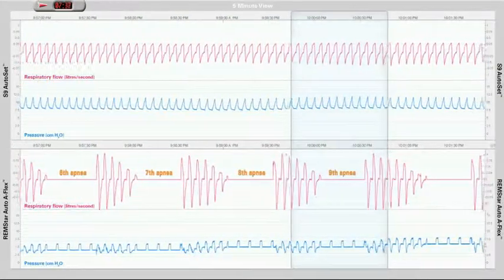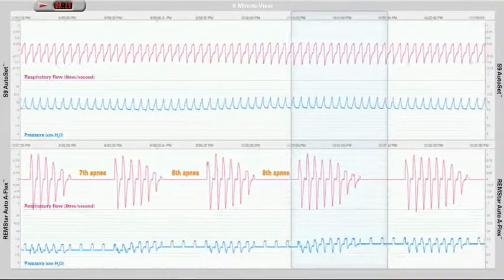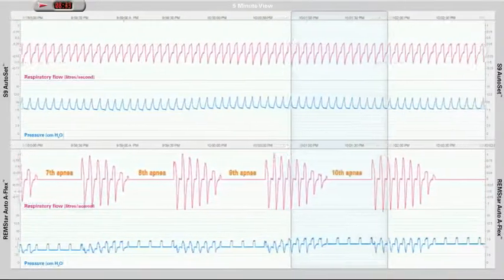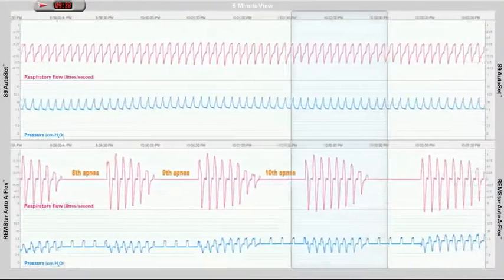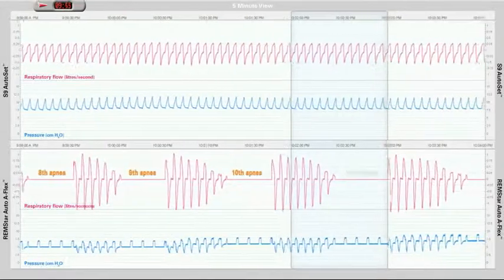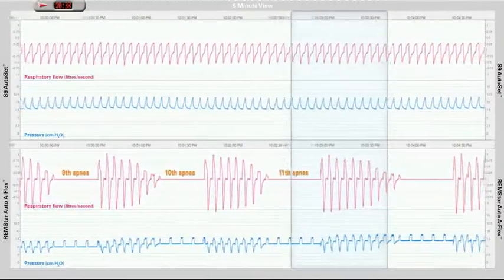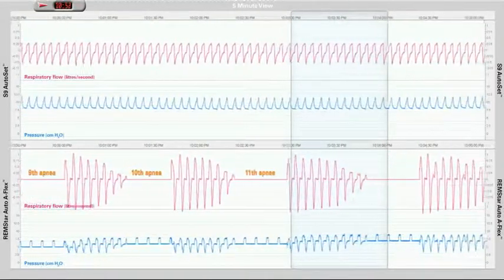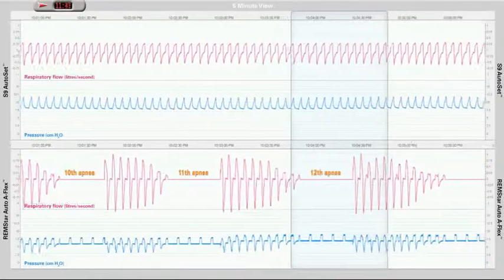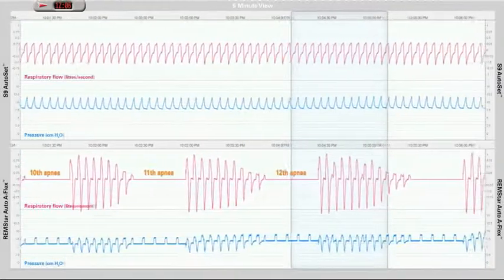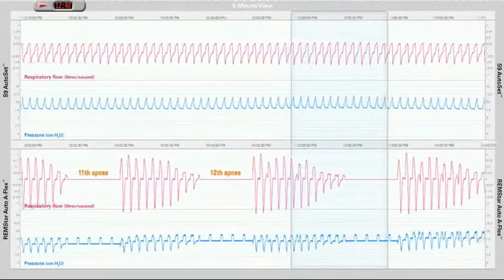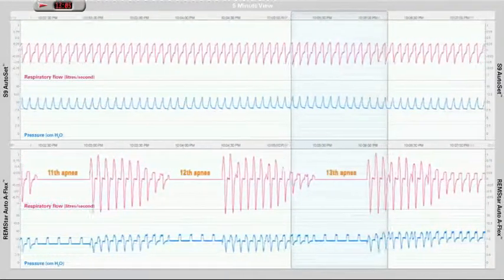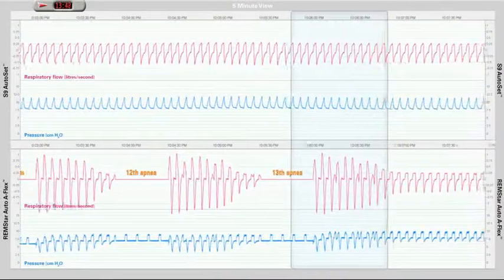The Remstar Auto patient continues to have apnea after apnea for a further 9 minutes. In total, the Remstar Auto patient has 13 obstructive apneas before the Remstar Auto device reaches a treatment pressure of 10 cm.